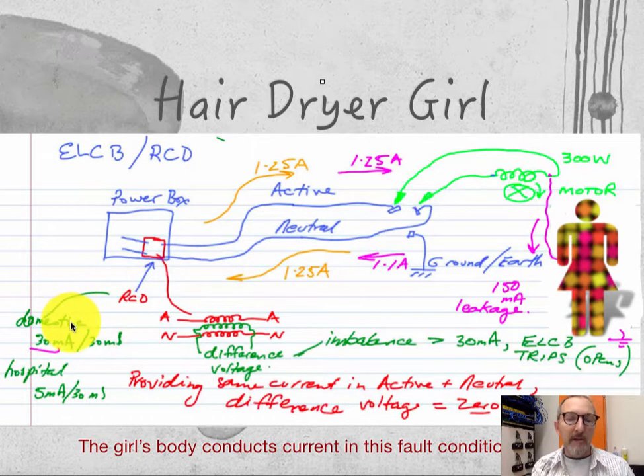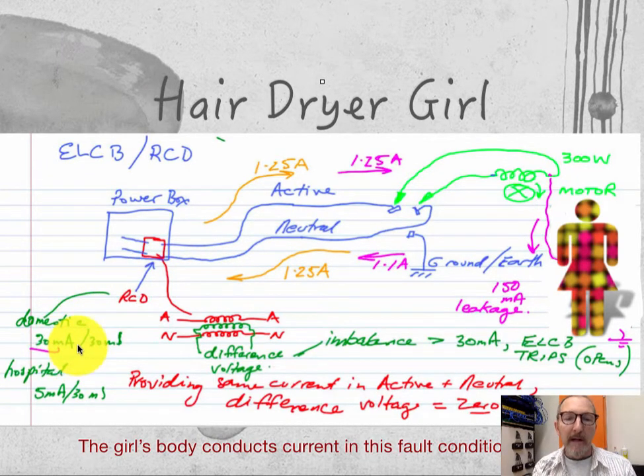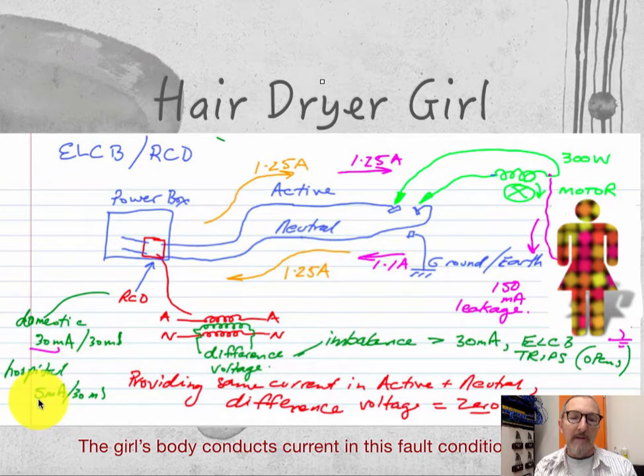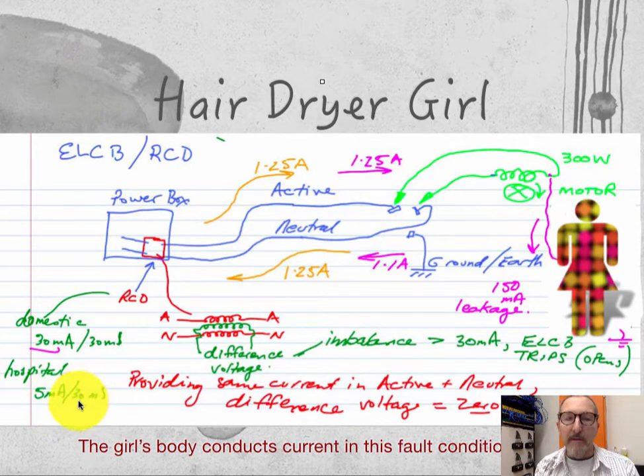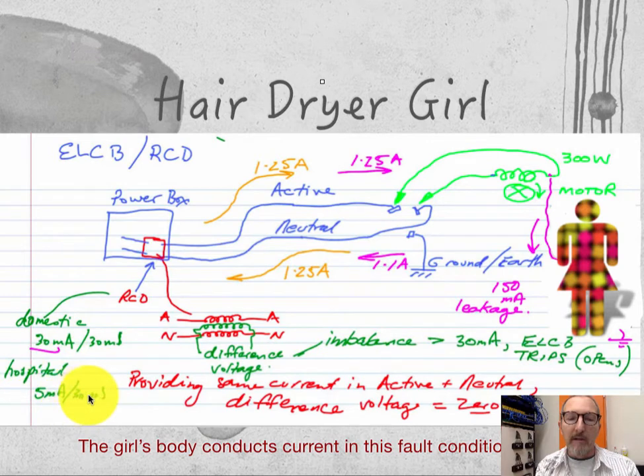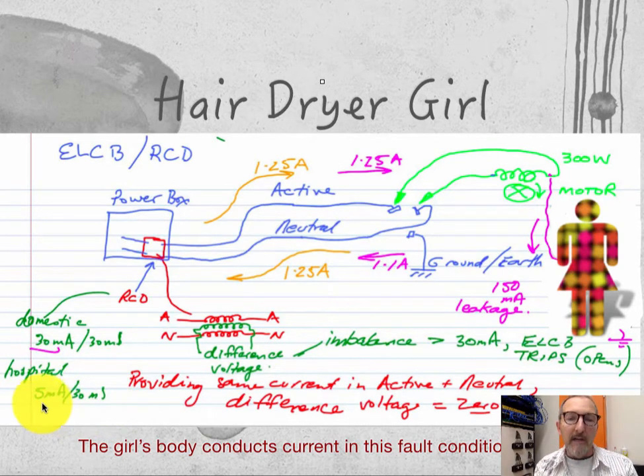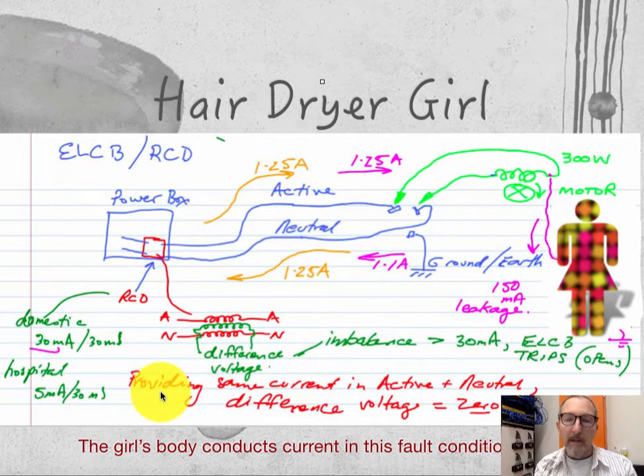In domestic situations, ELCBs trip at 30 milliamps and they trip within 30 milliseconds. In hospital situations, I believe they trip at 5 milliamps within 30 milliseconds — though you'd have to check the AS3000 regulations to confirm that is current.